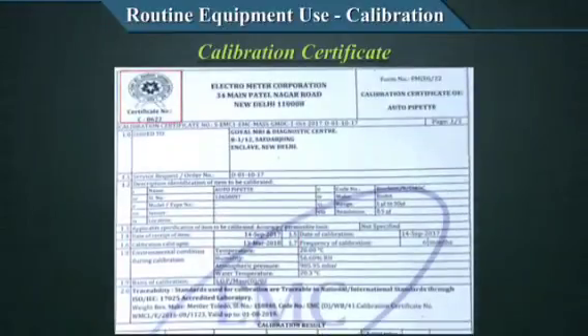Now we have the authority under which the certificate is issued. In this case, there is an NABL symbol since the calibrating agency is NABL accredited. NABL accreditation here means accreditation to the standard 17025 that we have talked about in the earlier discussion. I hope you understand the components that should be checked out on calibration certificates, and all these different things, the degree of uncertainty, the traceability and all other things, should be verified by the laboratory before accepting the certificate and accepting the equipment back after calibration.